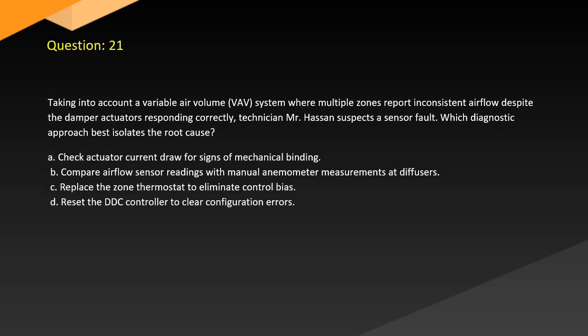Question 21. Taking into account a variable air volume (VAV) system where multiple zones report inconsistent airflow despite the damper actuators responding correctly, technician Mr. Hassan suspects a sensor fault. Which diagnostic approach best isolates the root cause? A. Check actuator current draw for signs of mechanical binding. B. Compare airflow sensor readings with manual anemometer measurements at diffusers. C. Replace the zone thermostat to eliminate control bias. D. Reset the DDC controller to clear configuration errors.